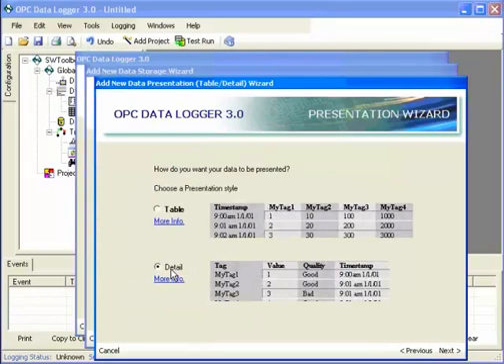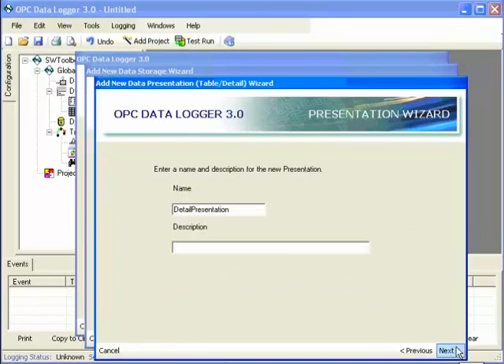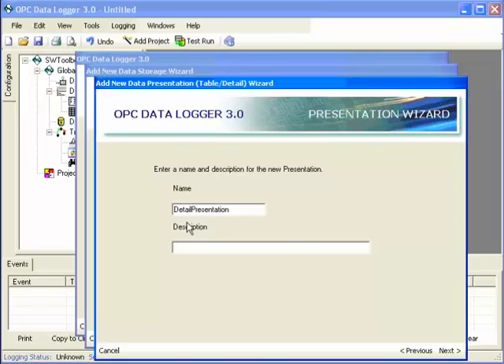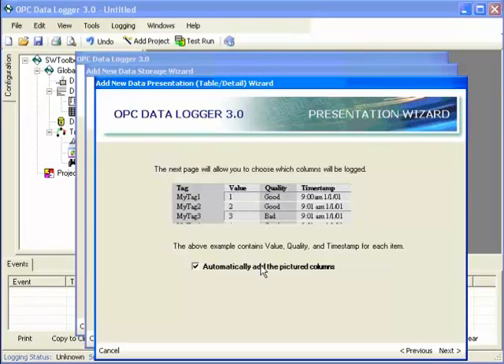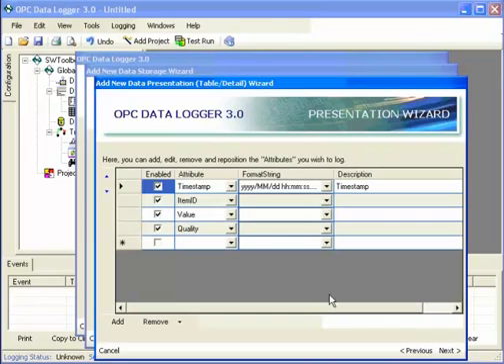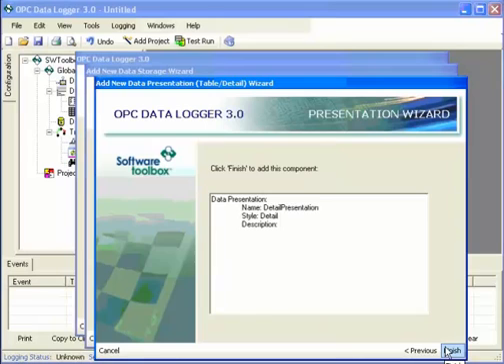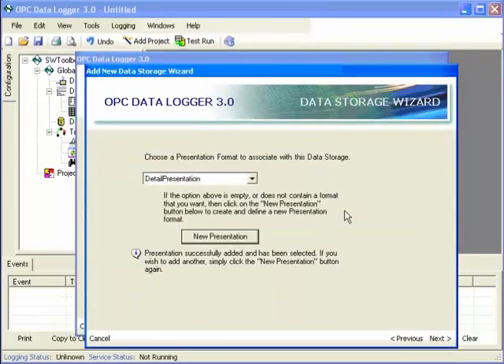We recommend detail mode. Here I can change the name of my presentation. I'll just leave it as the default. For every item, I want to log a tag name, value, quality, and timestamp. And by having this box checked, I'll automatically add those four attributes. So for every item I'm going to log, I'm going to see these four attributes in the text file.